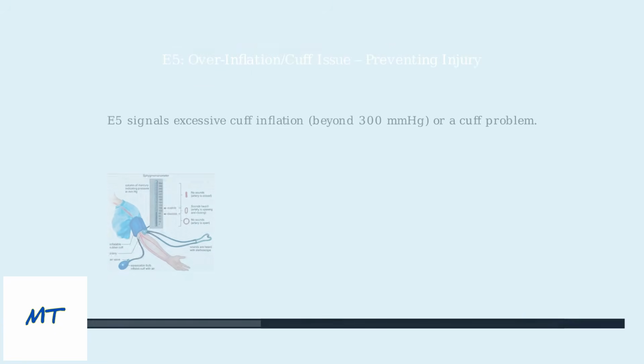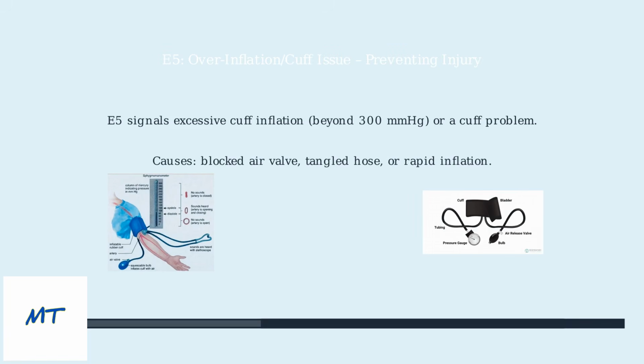E5 indicates excessive cuff inflation beyond 300 millimeters of mercury, or detects a problem with the cuff's functionality. This error may stem from a blocked air valve, a tangled hose, or rapid inflation. Check for any obstructions in the air path and ensure the hose is not kinked. If the issue persists, the cuff itself may be faulty and require replacement. This error is a safety feature to prevent user injury.